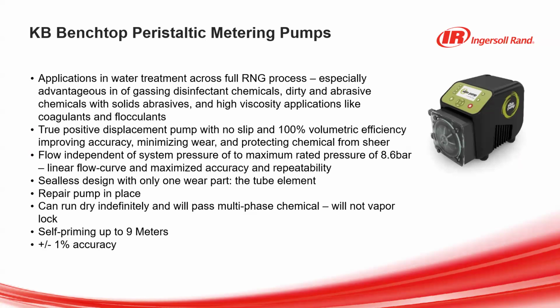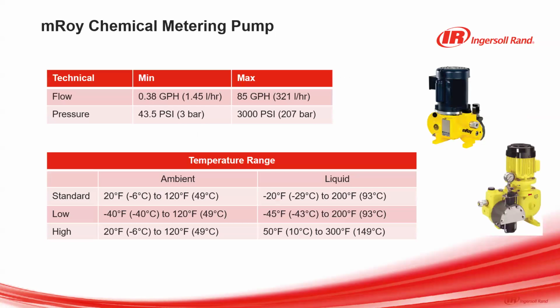Some of the applications and advantages of the peristaltic pumps include water treatment across the RNG process. Again, especially advantageous in off-gassing disinfectant chemicals or dirty and abrasive chemicals where there's solids or abrasives involved in the chemistry, and high viscosity applications, especially flocculants and coagulants in the water treatment process. This is a true positive displacement pump, meaning you're going to get a significantly higher degree of accuracy and repeatability out of the pump, and be able to maximize the use of chemistry in process and ensure reliability throughout the entire system. It's also a sealless design. So this means that the use of the pump and the maintenance of the pump is minimized.